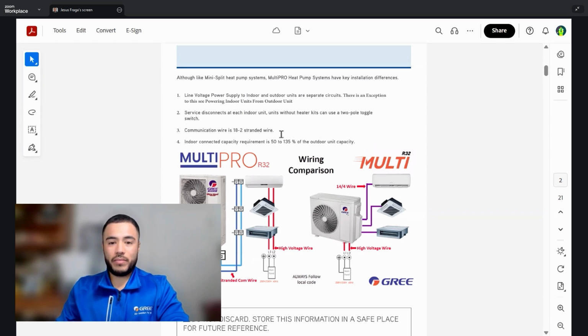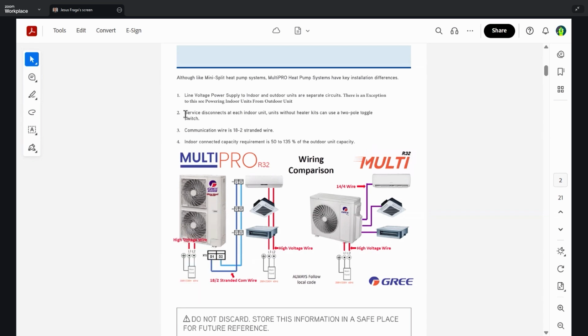To clear some other information here on this page, we recommend that you have service disconnects at each indoor unit. Those units are going to be units that do not utilize heat kits. The reason for that is because the amperage that the heat kit will produce will not be capable of the wire that is supplied from the outdoor unit. There's an exception to this, and as I stated earlier, we'll see on the next page what I'm referencing to.